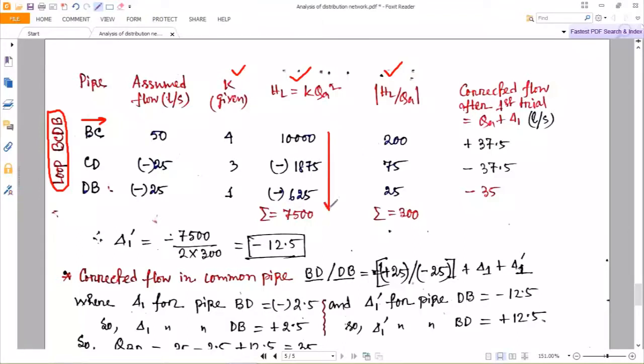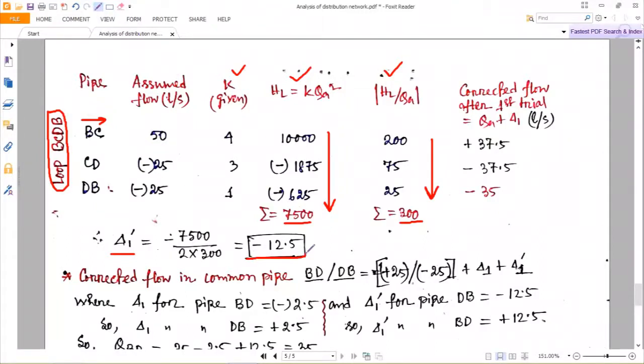Summation of h_L for loop 2: 10,000 − 1,875 − 625 = 7,500. Summation of h_L/Q_a = 300. The correction for the first trial, second loop: Δ₁' = −12.5. Apply this to single pipes: for pipe BC, assumed flow 50, apply −12.5, corrected flow = 37.5. For pipe CD, assumed flow −25, apply −12.5, corrected flow = −37.5. Now come to the common pipe BD/DB.